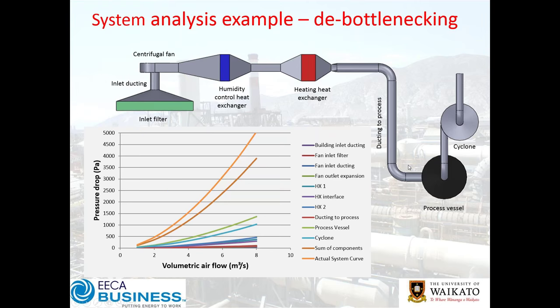Coming back to our example: the first cab off the rank is the thousand pascals in the system effect. It's a matter of looking at where these big losses occur. At a number of New Zealand plants we've been involved with, it's not uncommon to have 1,000–1,500 pascals of pressure drop across a very short transition piece due to poor duct design, nasty turbulence, eddies, and dead flow zones. When you identify these, you can be very targeted, freeing up capacity or saving a lot of energy.